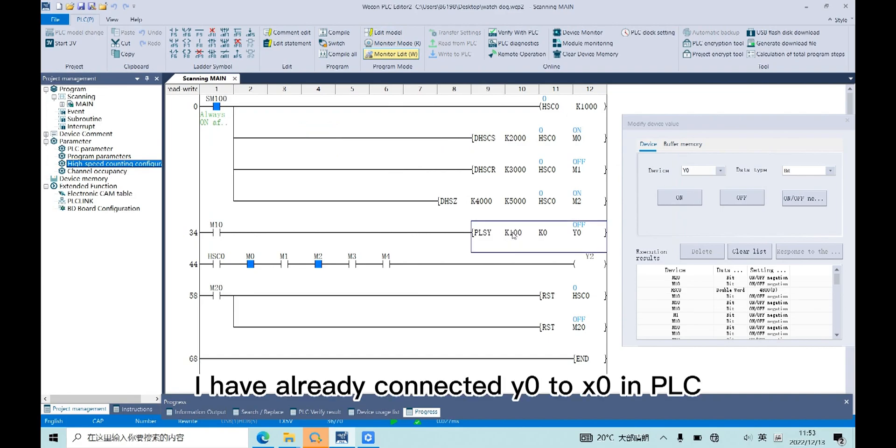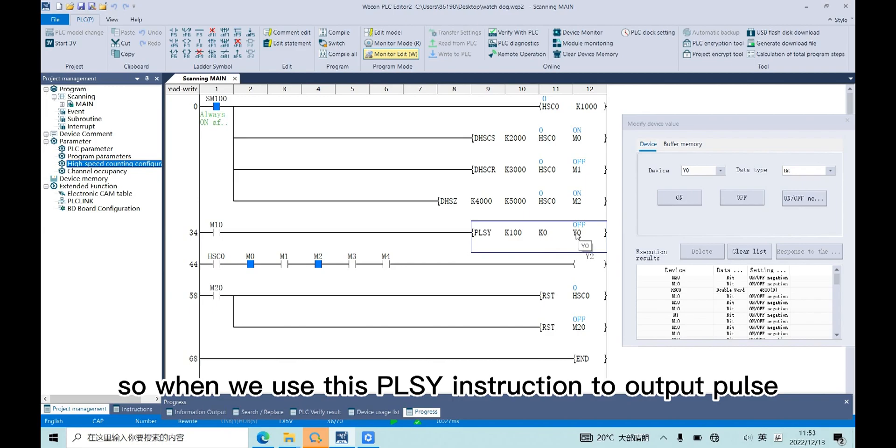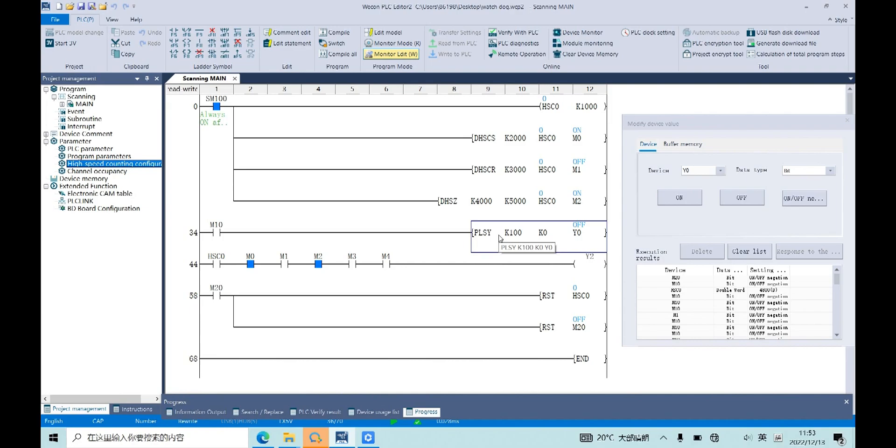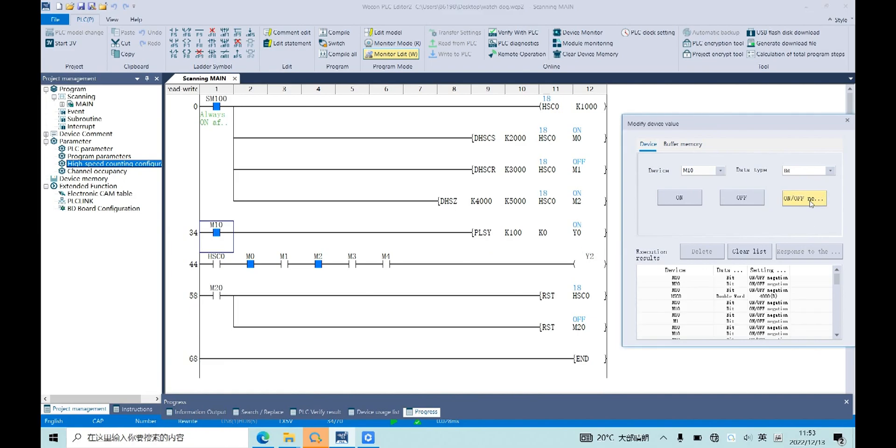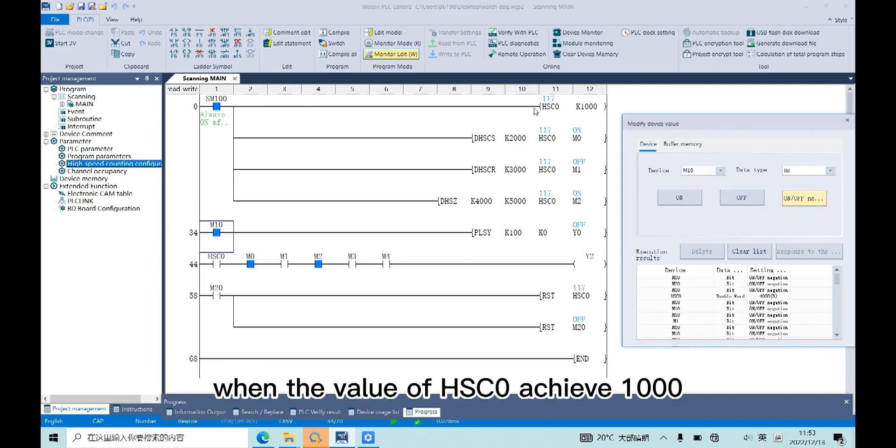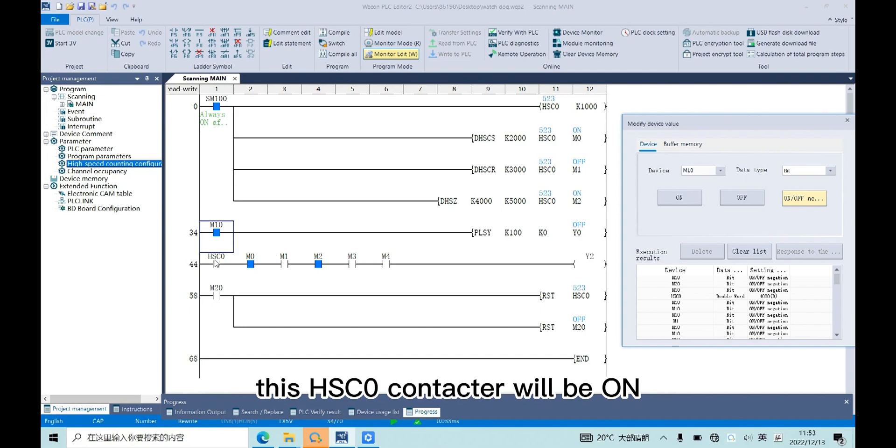I have already connected Y0 to X0 in PLC, so when we use this PLSY instruction to output pulse, HSC0 will begin to count. When the value of HSC0 achieves 1000, the HSC0 counter will be on.